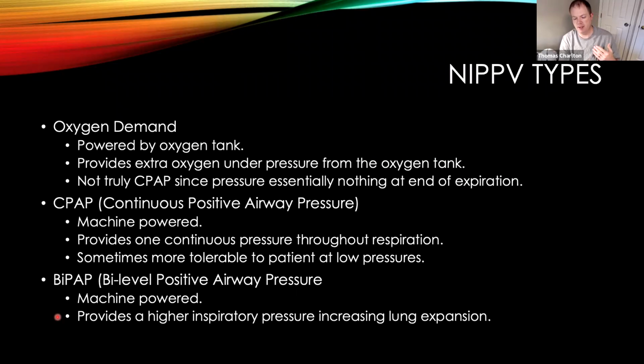However, when you reach your maximum and begin to exhale, the machine senses that as well. It senses that there's now a positive pressure behind it, and is then going to spool the motor down so that it's easier for you to actually do your exhalation. Because trying to push against somebody at those high pressures can be really tiresome and not very comfortable. So it spools the pressure down a little bit, allowing you to exhale more easily.